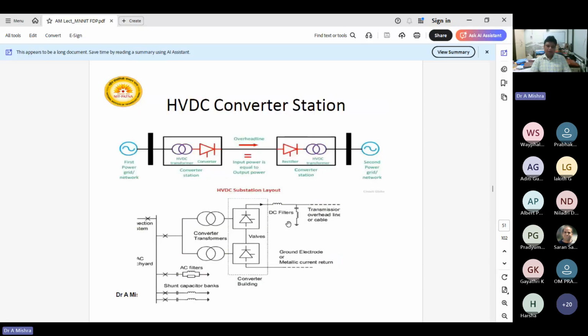Now, coming to the converter station, what are the things that are being used? Your first AC source is there, and the second AC source is there. In between, you have two stations: converter 1 and converter 2. All the time you cannot say rectifier and inverter, because of the power flow direction. This converter will be working as rectifier and this converter as inverter, but if the power flow direction changes, this converter will be working as rectifier and that one as inverter. So you can call them converter 1 and converter 2. Based on the requirement, they change operation by changing the value of the firing angle.